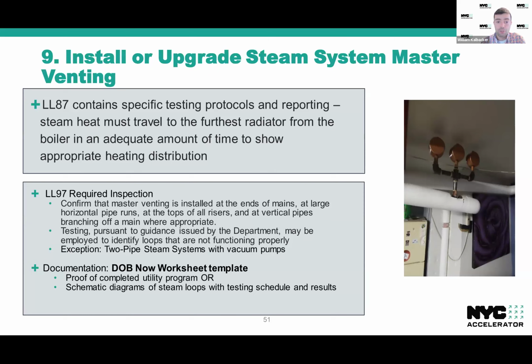For Local Law 97, the required inspection is that master venting is installed at the ends of mains, at large horizontal pipe runs, at the tops of risers, and at vertical pipes branching off where it's appropriate. Again, make sure that you're working with someone who knows what they're doing in installing vents, and that testing pursuant to guidance issued by the department may be employed to identify loops that aren't functioning properly. So if it's a little bit more involved, and you need a little bit more help identifying where to install the vents, that guidance is going to be forthcoming. Again, you do not have to install vents on two-pipe systems that operate with a vacuum.